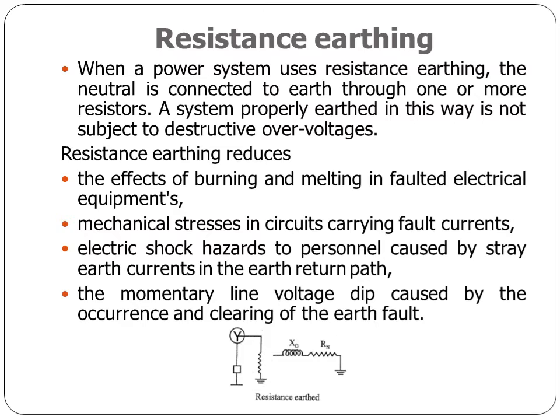What are the advantages of resistance earthing? The effect of burning or melting in a faulted electrical equipment can be avoided. Mechanical stress in the circuit carrying fault currents is also reduced. Electrical shock hazards to persons caused by stray earth currents in the earth return path are reduced. The momentary line voltage dip caused by the occurrence or clearing of the earth fault is reduced. So these are the advantages of resistance earthing.